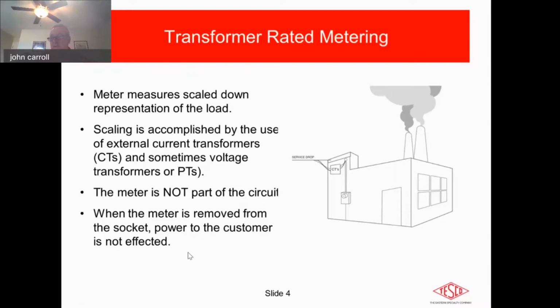So that's why we mentioned multiple times through this presentation that the CTs themselves are a vital part of this testing circuit. If anything happens at that CT position, it's likely to affect the metering, not so much the accuracy perhaps, but certainly the incoming current, which is part of the overall measurement. The meter in this case is not really part of the circuit, so it can be removed fairly safely. We see that quite frequently, and a meter can be tested that way as well. That's very normal. People do that too.